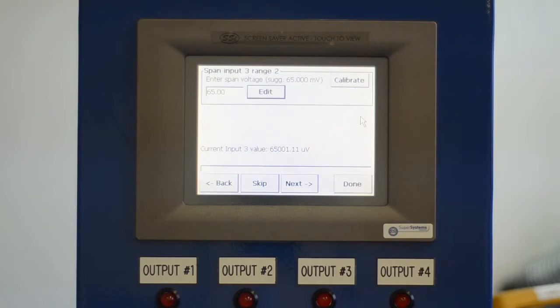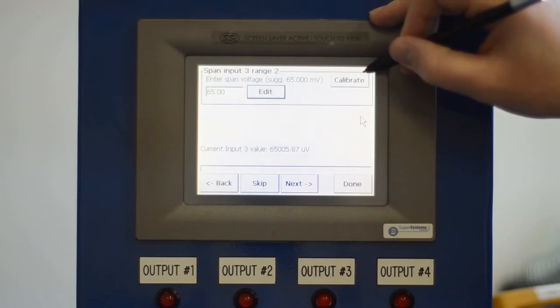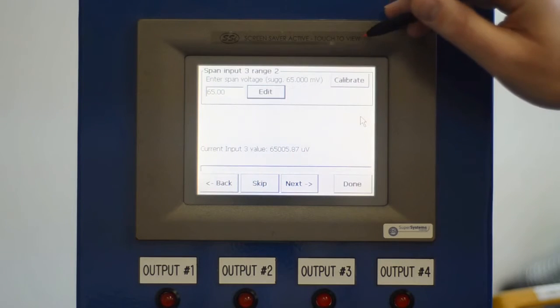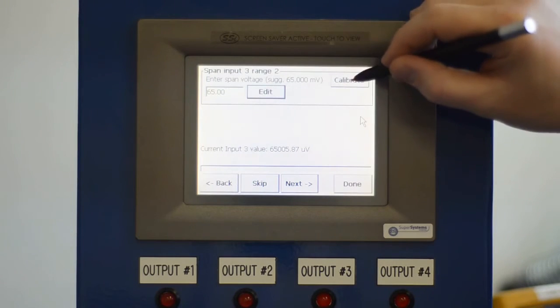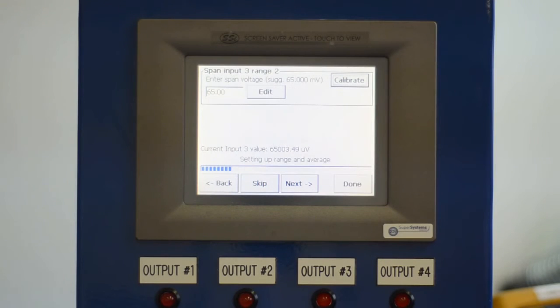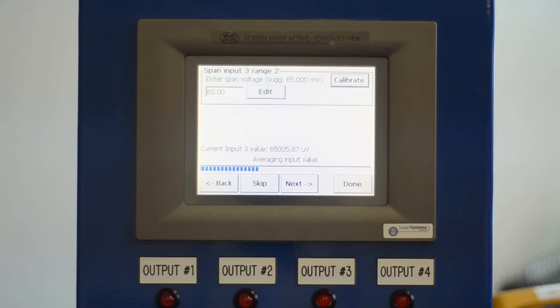I will give it a second here just to stabilize out. Once it has stabilized, I'll select the calibrate button. Let's get a little bit closer here, 65,000 even. Calibrate. Before you select calibrate, you want to make sure that you have the value that you are sourcing in. In this case, since we are sourcing in the 65 millivolts, we have 65 in that field. All of our sourcing for 0 and span is being done with copper wire.